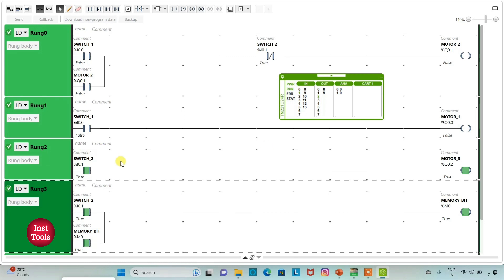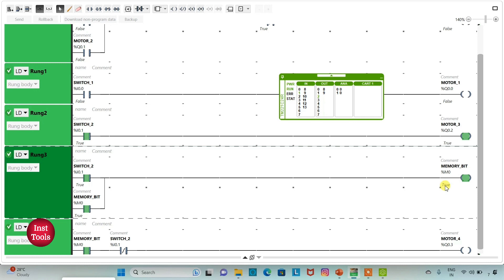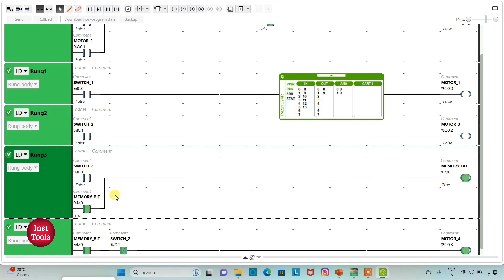When switch 2 is on, motor 3 will be on and the memory bit will also be on. When I turn off switch 2, the memory bit still remains true as we have latched it. When the memory bit is true and switch 2 is false, since we used a normally closed contact — in a false state, current will flow through it — and motor 4 will be on.